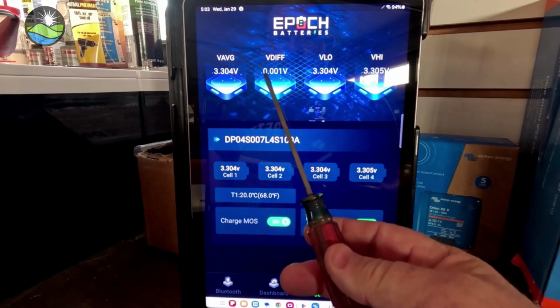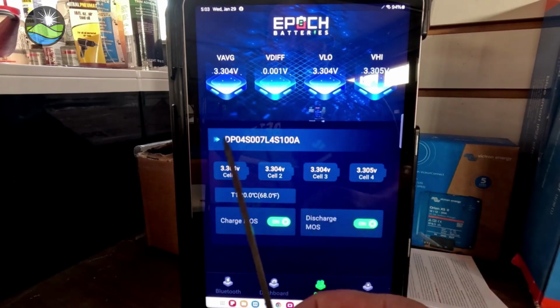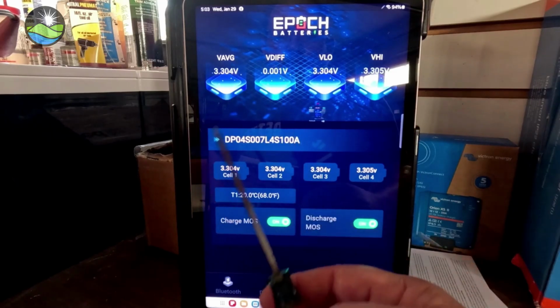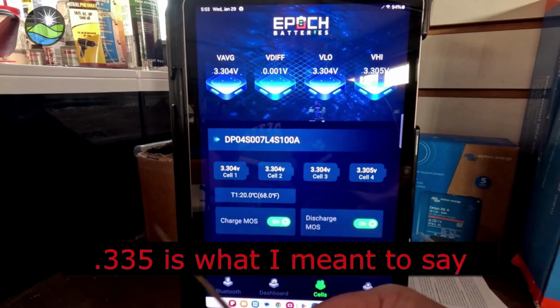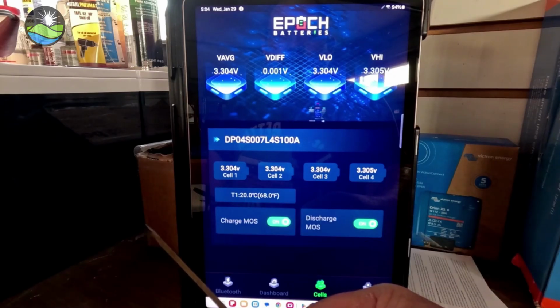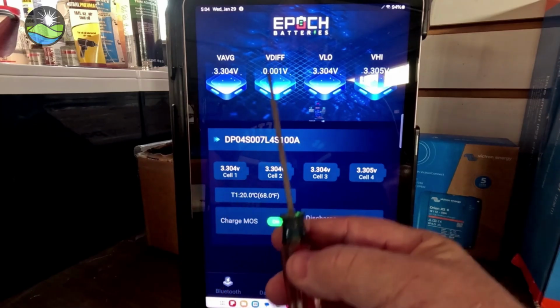This tells you the health of the battery as a whole. If you have a huge differential here, like say 0.0335 or something like that, you've got a problem on your hands. Either you're not charging it right over time, you're short cycling it, or there's an actual problem with the battery, and that's how you'd tell.